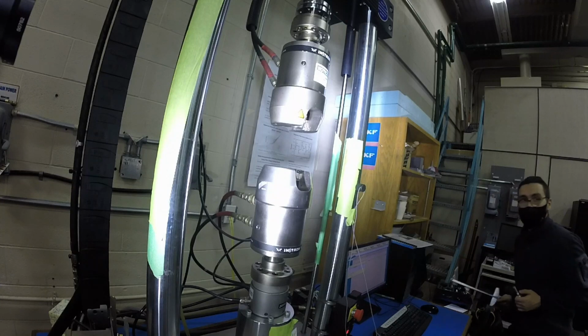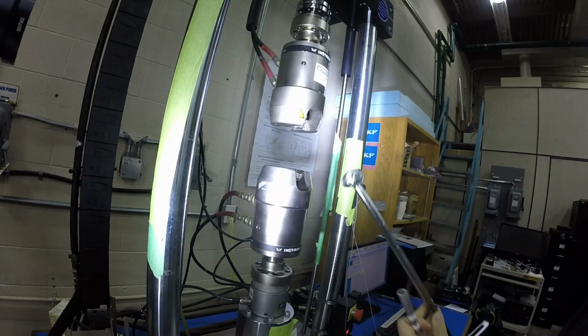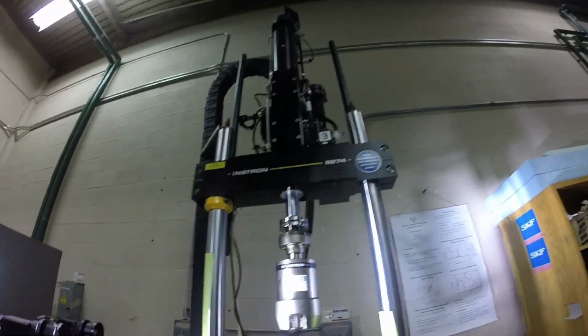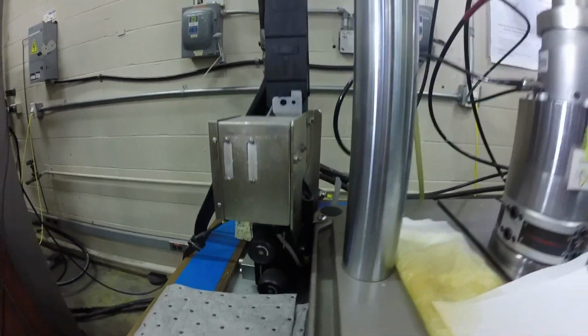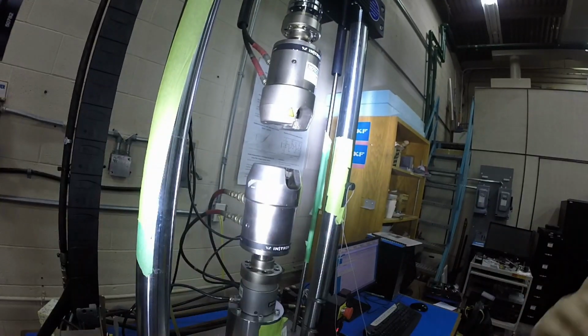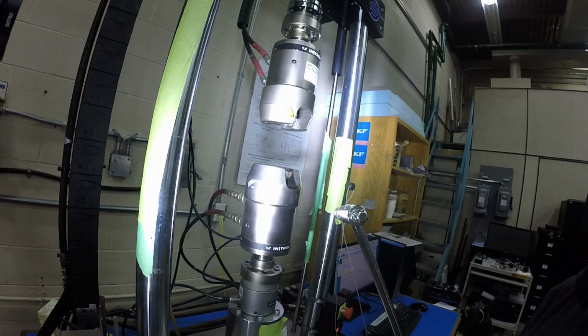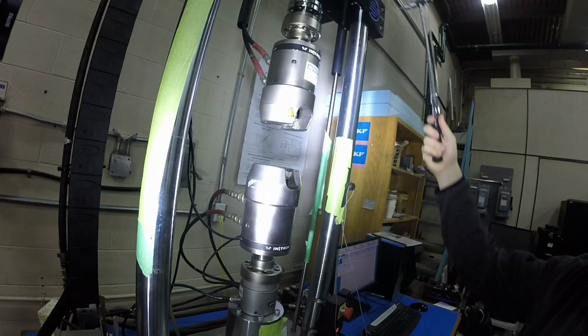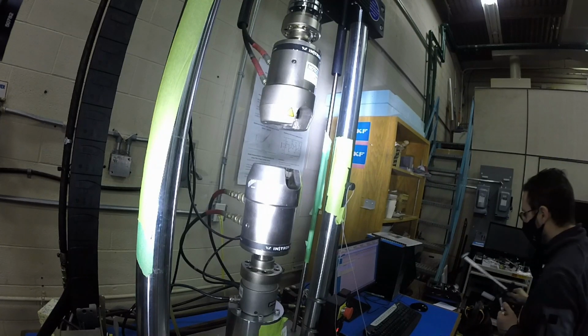needing of adjustment, you can use the torque wrench or an Allen socket to remove the top 4 bolts on the crosshead there, and you can loosen them, as well as this yellow collar. And what that will allow you to do is then use the adjustment here on the side of the machine to raise and lower the upper crosshead to accommodate whatever length of sample that you want. Once you put it back together, you want to make sure that you obviously tighten the collar that prevents it from sliding down, the yellow collar, and then you want to tighten with the torque wrench here. You want to tighten the crosshead to 30 foot-pounds of torque in a crisscross fashion.